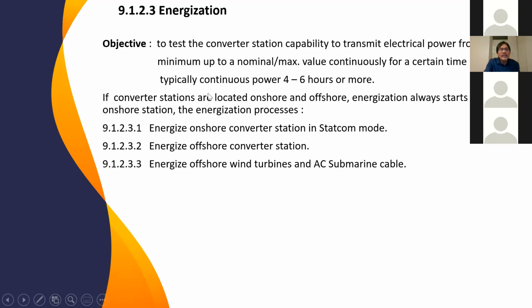If the converter station is located offshore and onshore, energization always starts from the onshore substation. There are 3 steps of processes here. The first step, we have to energize the onshore converter station in STATCOM mode. The next one, we energize the offshore converter station. And then the last one, we energize the offshore wind turbine and submarine cable.